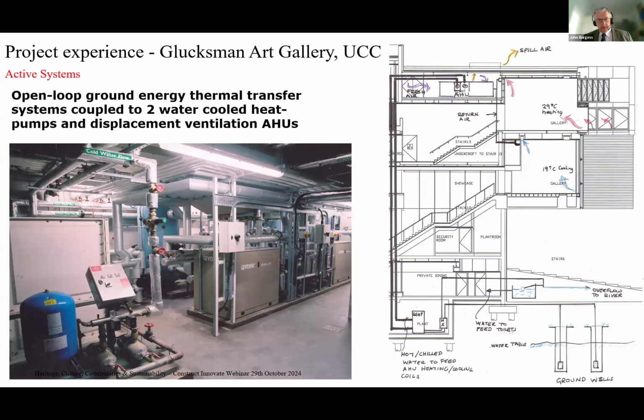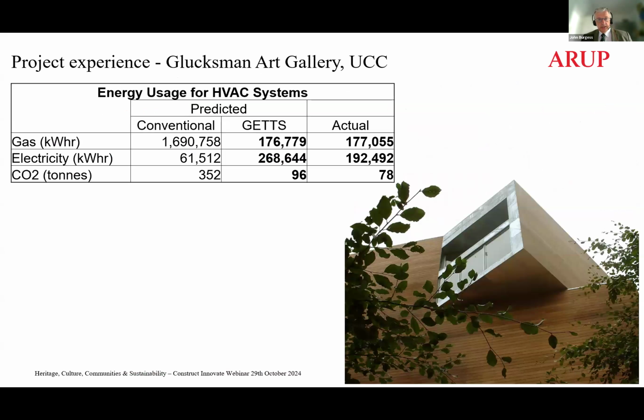Following that, the Glucksman Art Gallery, where we looked at using geothermal heat pumps coupled with displacement ventilation systems, where the lowest cooling temperature was 19 degrees and the highest heating temperature was 29 degrees. And these much lower operating temperatures than you would typically see in a conventional system have led to a massive decrease in energy use. Looking at the conventional system, we were looking at 1.7 gigawatt hours of gas. That was reduced to just shy of 180 megawatt hours.